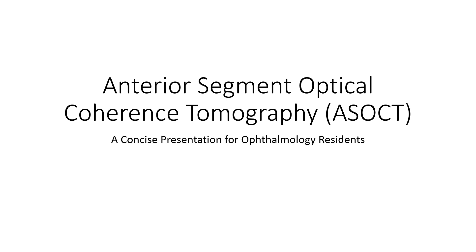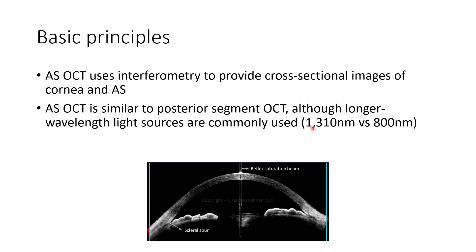This video discusses anterior segment optical coherence tomography, that is ASOCT. ASOCT uses interferometry to provide cross-sectional images of the cornea and anterior segment. It is similar to posterior segment OCT, although longer wavelength light sources are commonly used. In ASOCT, a wavelength of 1310 nanometers is used, whereas for posterior segment OCT, a wavelength of 800 nanometers is used.